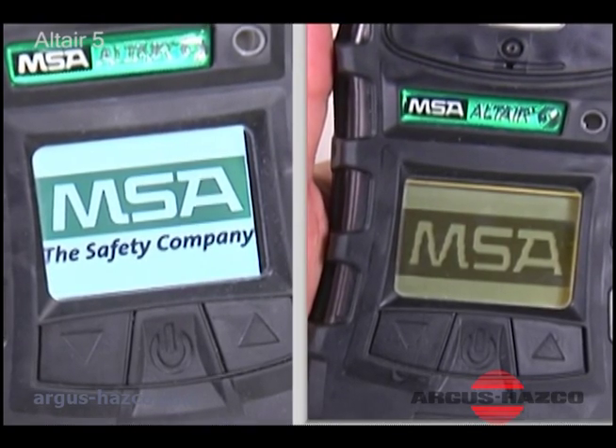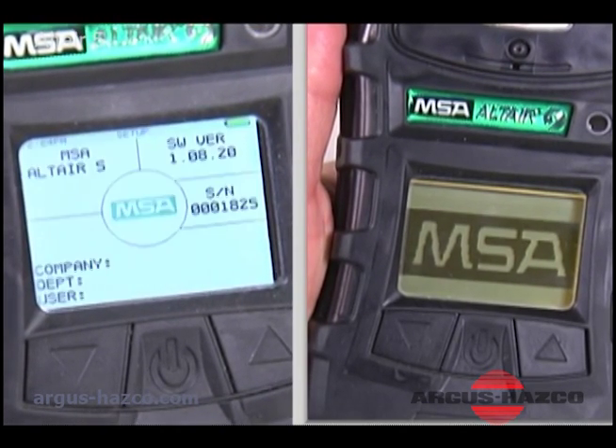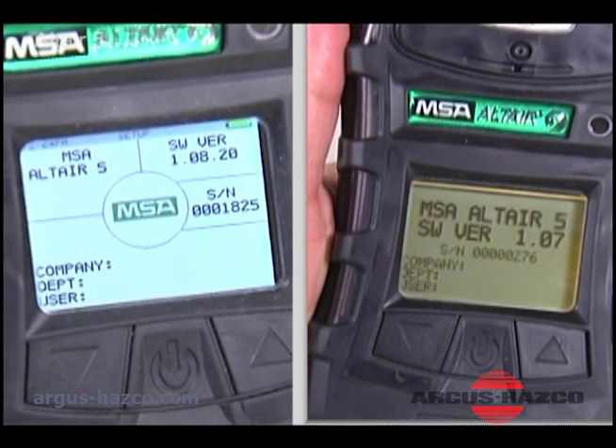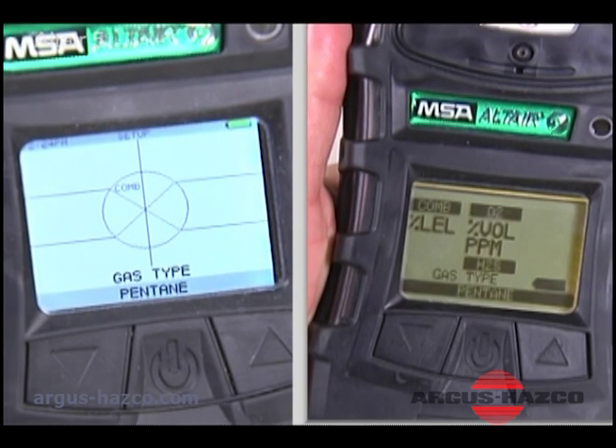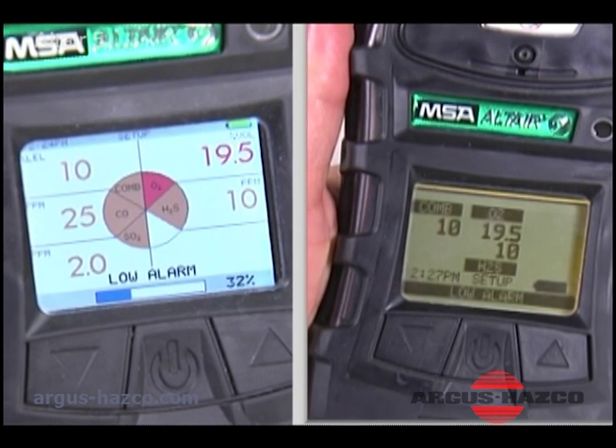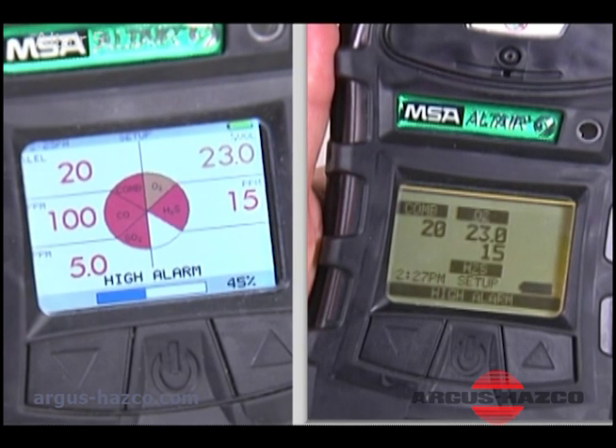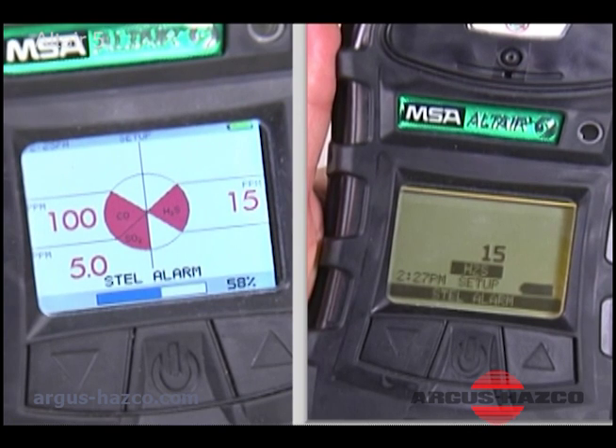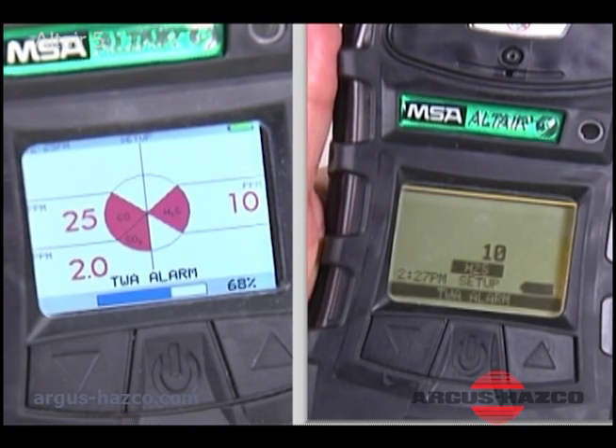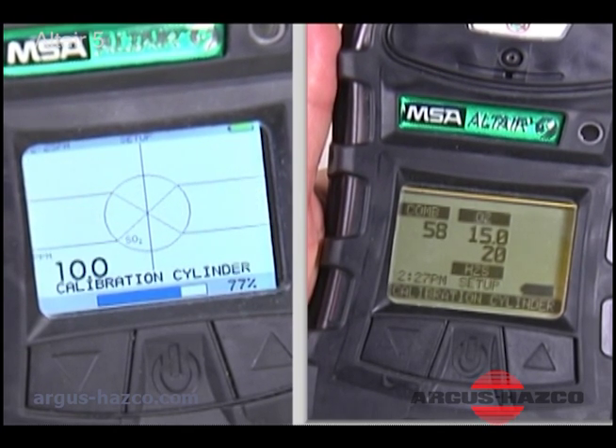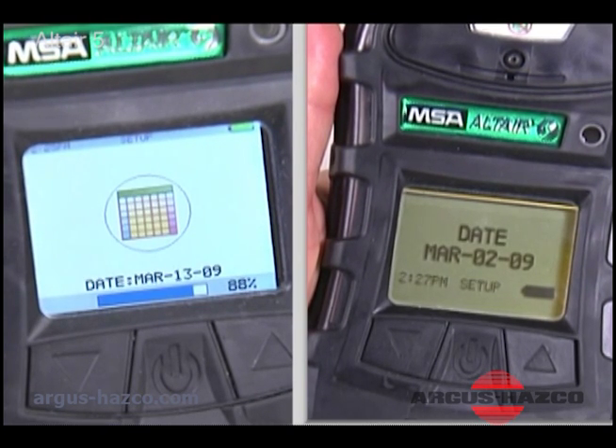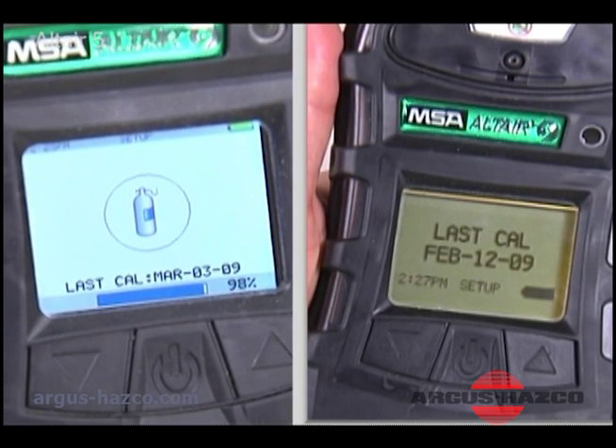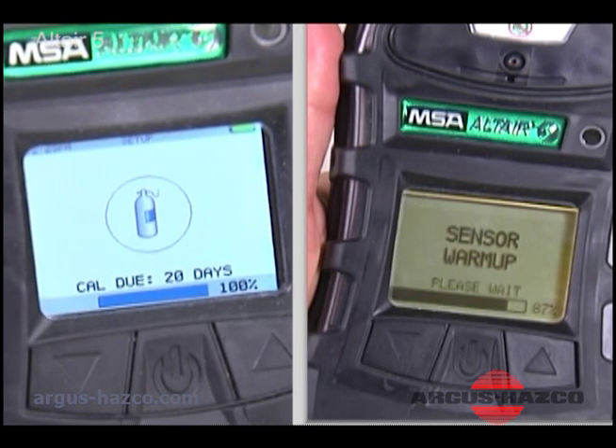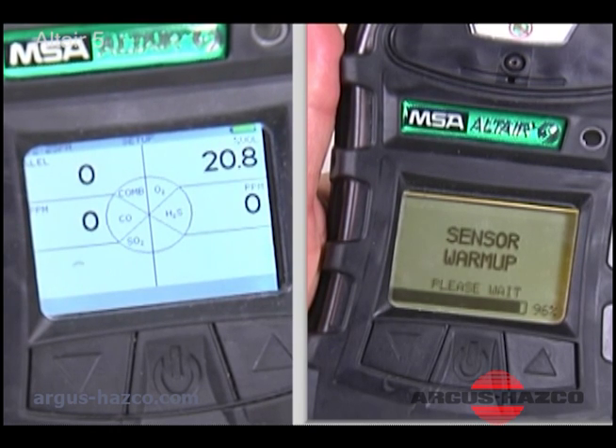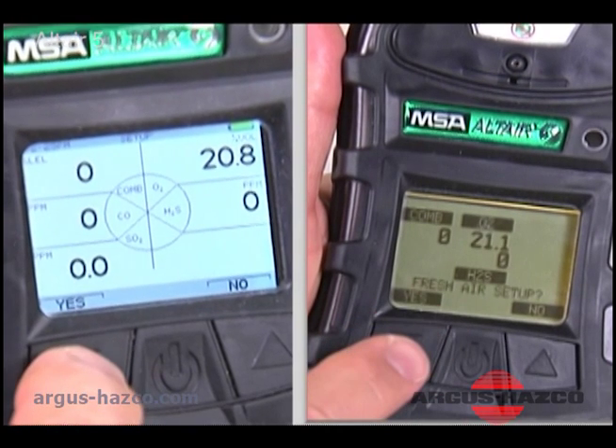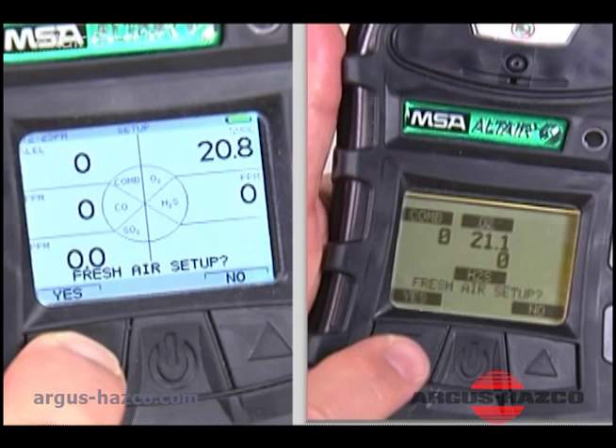If the instrument does not detect a missing sensor, the turn-on sequence continues and the instrument displays the MSA logo, software version, instrument name and serial number, company name, department, and username. It identifies the combustible gas sensor installed, low and high alarm set points, short-term exposure limit or STEL, and time-weighted average or TWA alarm set points, calibration cylinder settings, the current date, the last calibration date, the date the next calibration is due, sensor warm-up progress, and a fresh air setup prompt. Press the down arrow button to enter fresh air setup.